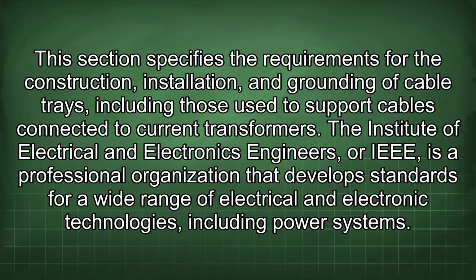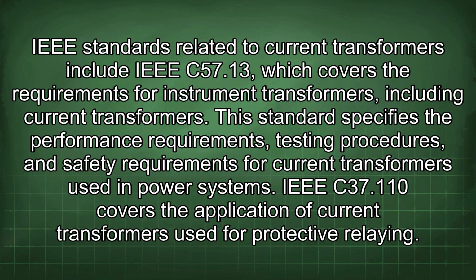connected to current transformers. The Institute of Electrical and Electronics Engineers, or IEEE, is a professional organization that develops standards for a wide range of electrical and electronic technologies, including power systems. IEEE standards related to current transformers include C57.13, which covers the requirements for instrument transformers, including current transformers. This standard specifies the performance requirements, testing procedures, and safety requirements for current transformers used in power systems.